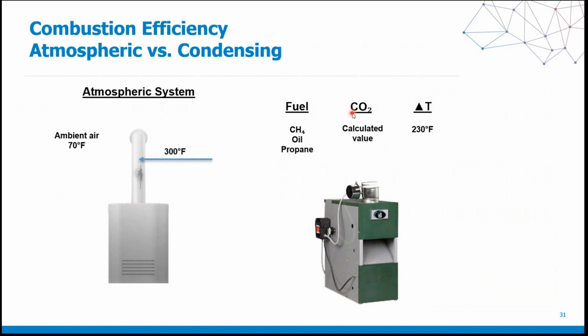Remember, I told you before, oxygen is king. So it's calculated based on the oxygen percentage, but it's also calculated based on the fuel type, or the coefficients that are assigned to the fuel. So if you have the proper fuel type selected, the calculation will be correct when your CO2 number is calculated. And the last thing we talk about is delta T, otherwise known as change in temperature. In that delta T, when we talk about combustion efficiency, is a change from the ambient room, in this case, to the actual stack temperature.